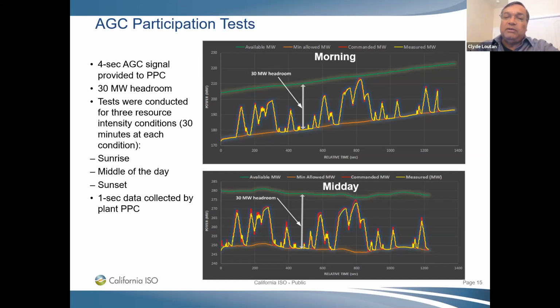Now, what's really interesting about this plot, also, in the US, we pay units provided in regulation not only for the capacity, but we also pay for how well they can follow a dispatch instruction. We refer to that as a mileage charge, which means how many times they move up and down. You measure that and see how well these plants can follow a dispatch instruction. The solar plants were able to follow those instructions about 94% of the time. The best gas plant was able to do that about 60% of the time, and the hydro was right about the same. So right there, solar plants demonstrated that they can follow dispatch instructions a lot better than conventional units. So again, it was an eye-opener, and it's very encouraging for integrating renewables on the grid.